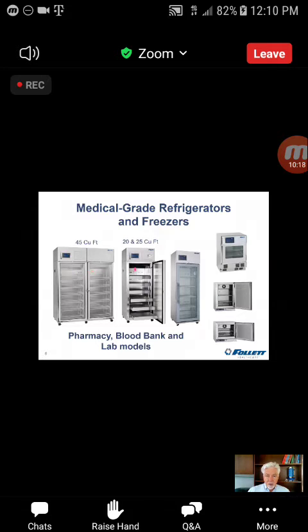The difference with the blood bank unit is because of the solid stainless steel drawers and the challenges they present to even air distribution. AABB knows that they want the temperature monitored at the top and at the bottom. So there is a second bottle and probe down at the bottom to monitor that temperature as well. That's optional on other units. You can get that if you'd like to, but it comes standard on the blood bank units.